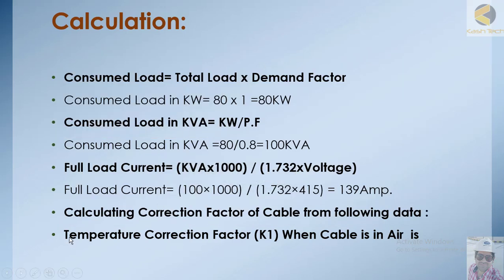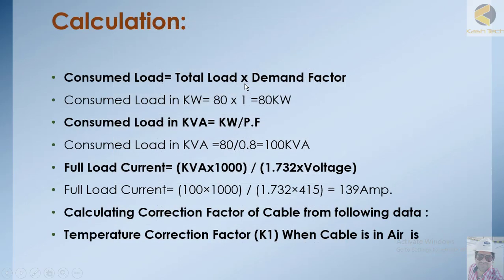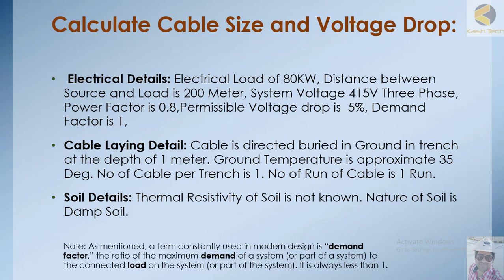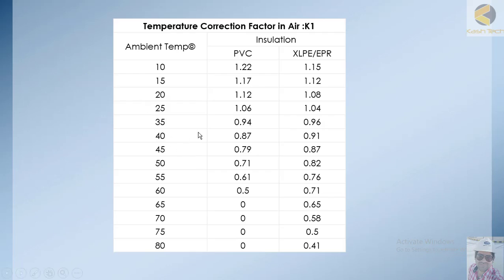Now let's look at the temperature correction factor K1. From the table, if the ambient temperature is 40 degrees and you are using PVC cable, you multiply the base current rating by 0.94. If you are using XLPE or EPR cable, you multiply by 0.96.